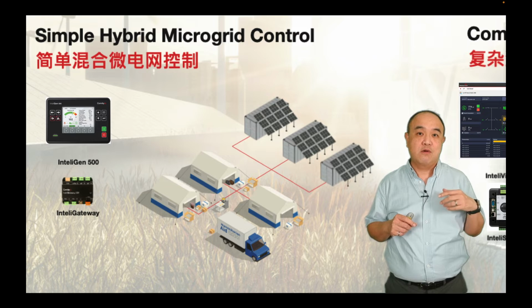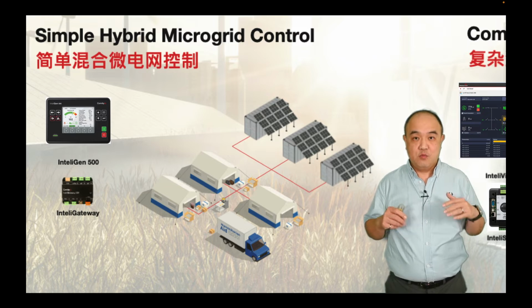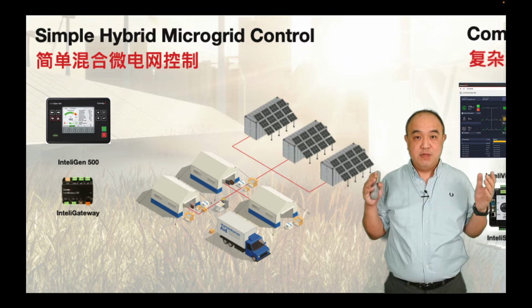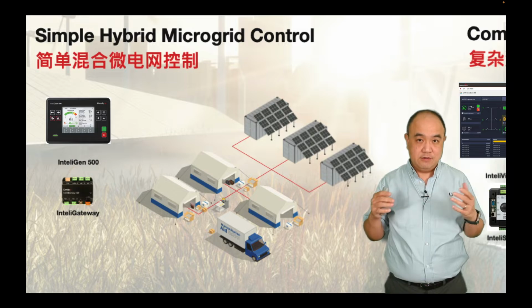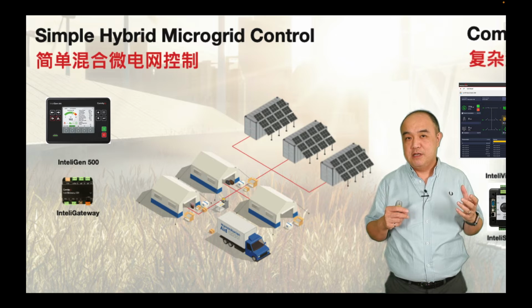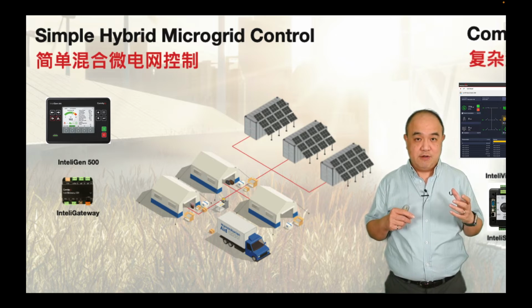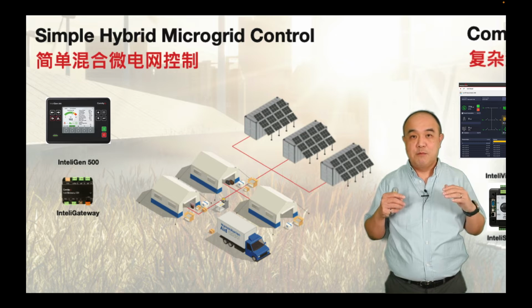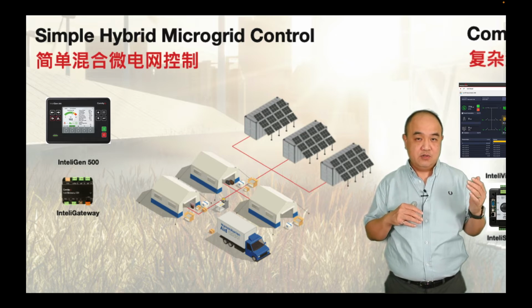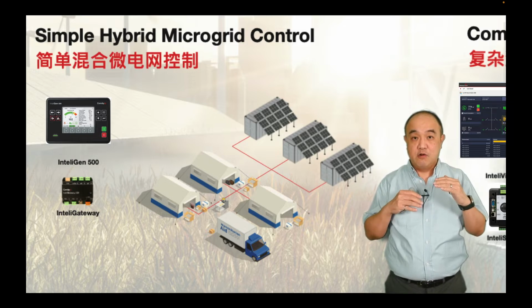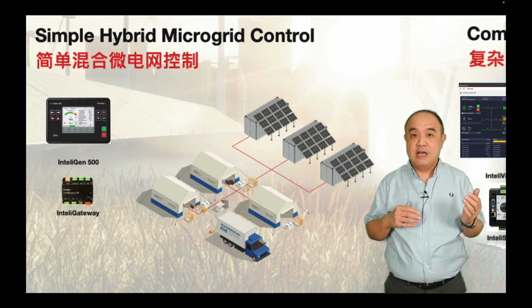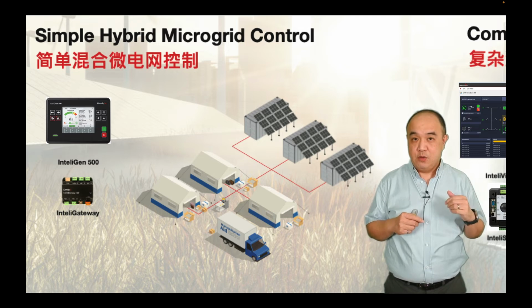This is for 1 genset with a bunch of PV panels. They don't parallel with each other, just 1 genset. These are typically for under 100 kilowatt small genset scenarios. The ComAp system will balance the load between the PV panels, the batteries, and the gensets to give you robust, consistent, and reliable power, also saving you diesel.